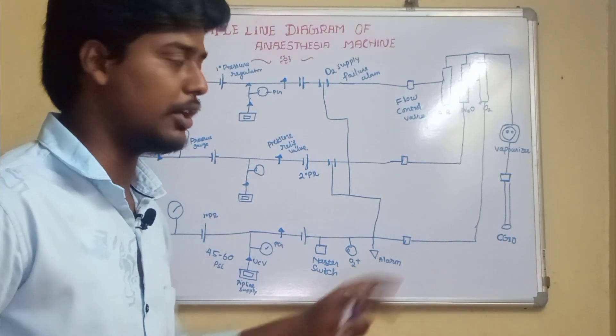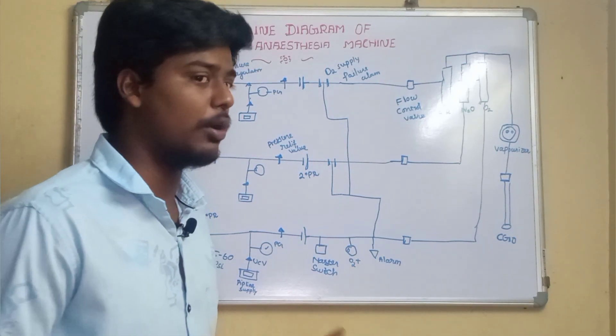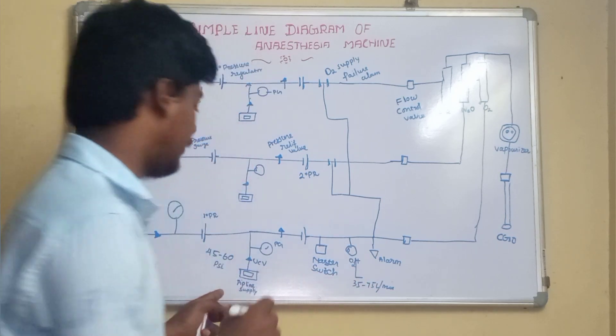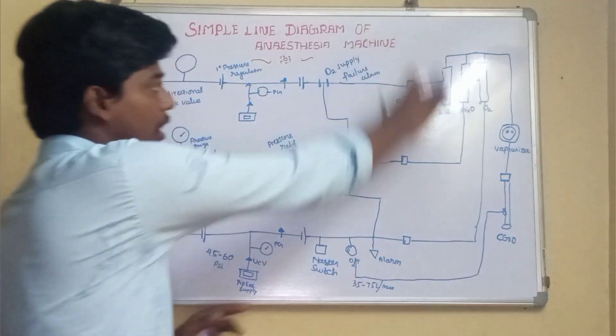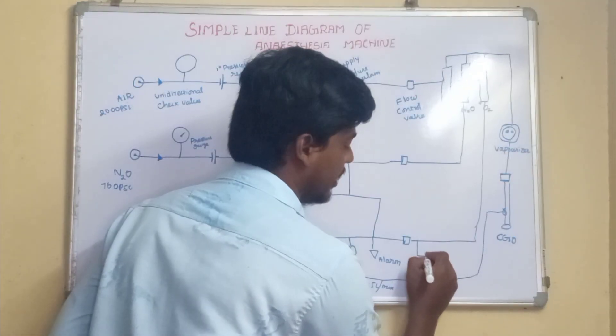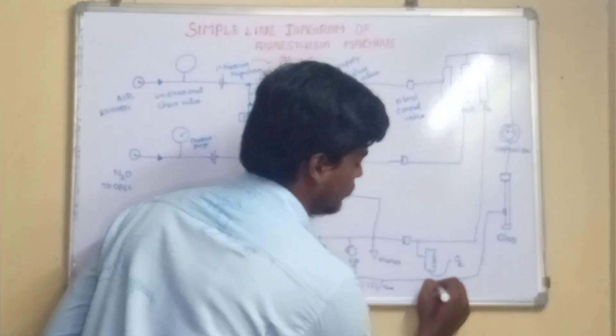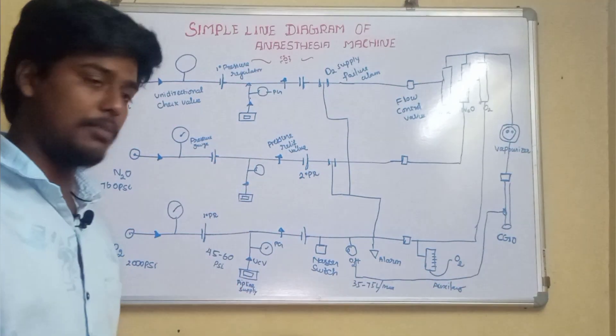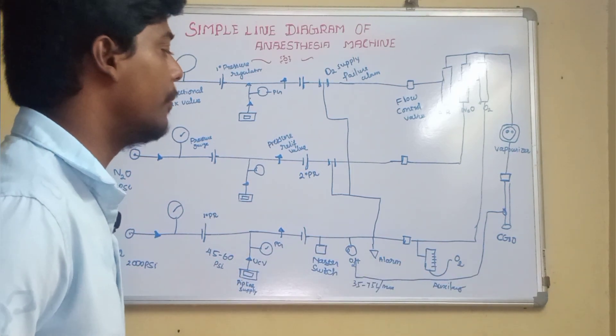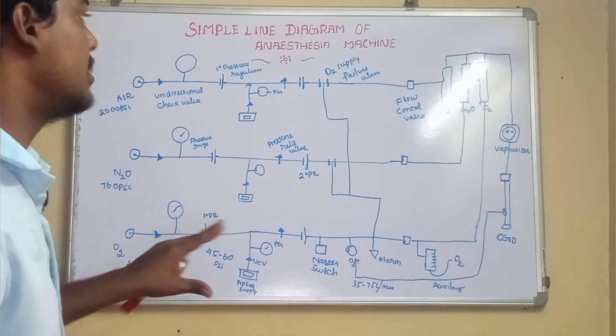At the common gas outlet, we connect breathing circuits or patient breathing circuits to provide anesthesia. The oxygen flush is an independent part of the anesthesia machine — it has a flow rate of 35 to 75 liters per minute and operates at 45 to 60 psi pressure. It connects directly to the common gas outlet, bypassing all other components in the line. There is also another independent component called the auxiliary O2 flow meter.